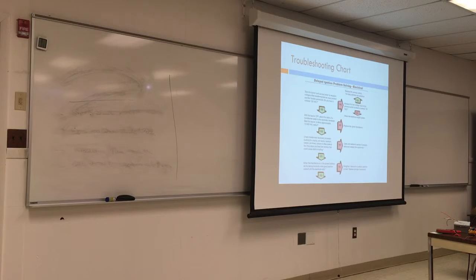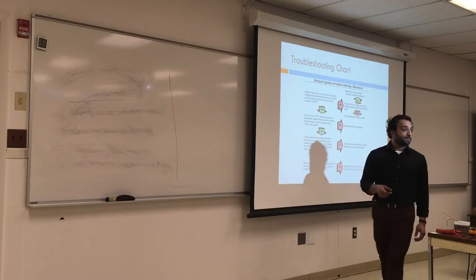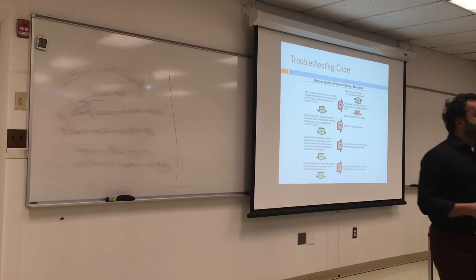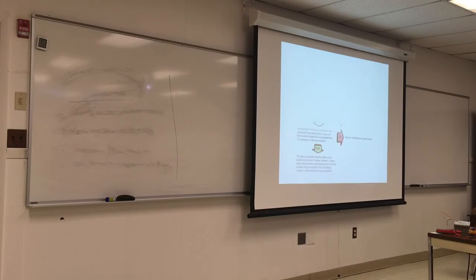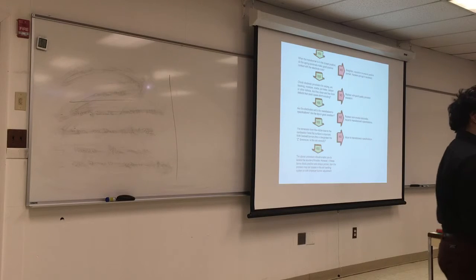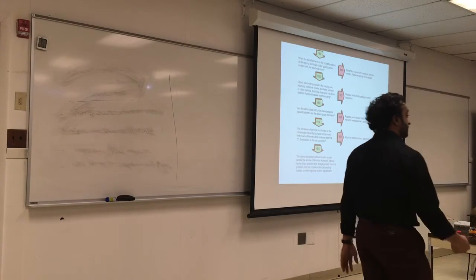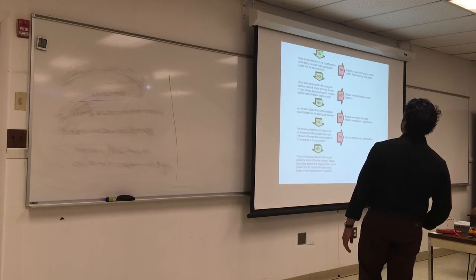So this issue is called delayed ignition. What happens with delayed ignition? How many times does the primary try to start the fire before it goes into lockout? 3 times. Excellent. It will try the first time and then stop. Then restart again and try. The 3rd time it will just go into lockout because something is wrong. And again, the first time when you start the boiler is the hardest one because everything is cold. It's not at operating temperature.